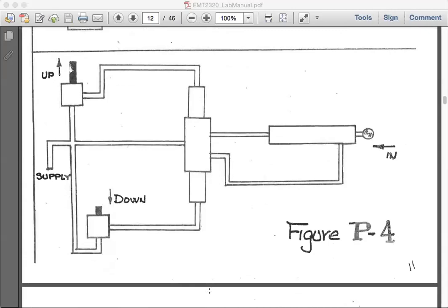When you activate the bottom push button, then you provide the pressure, and then basically you move the stem up. As the stem moves up, the pressure from the source goes through the top. So if the pressure moves through the top, then it pushes the piston out. As the piston is moving out, the pressure from the right chamber comes right here, stem is up, so the pressure from here vents through the venting opening at the bottom.